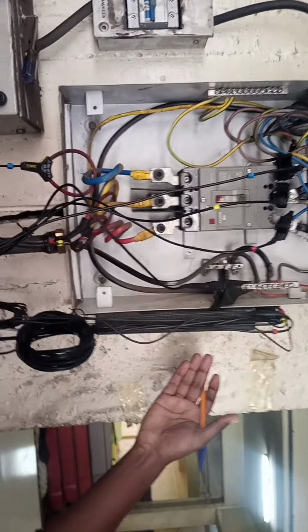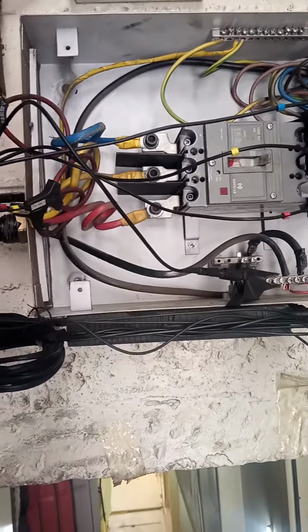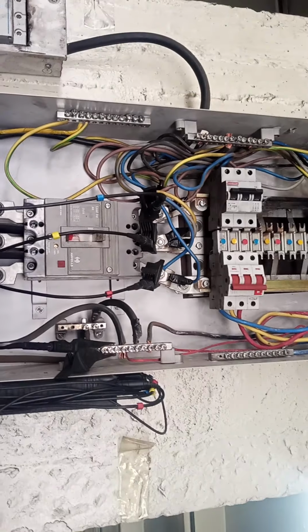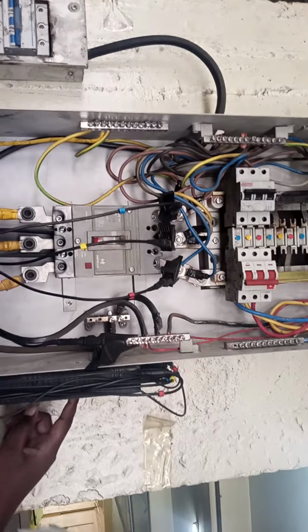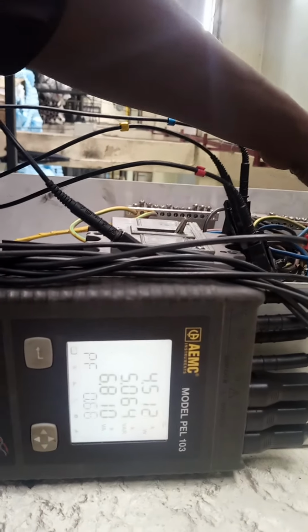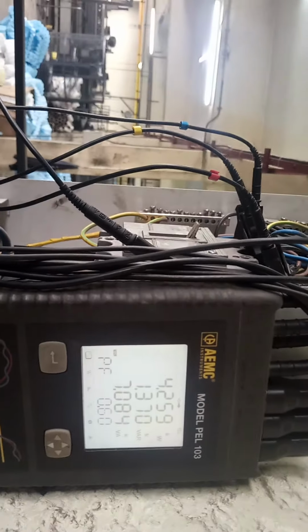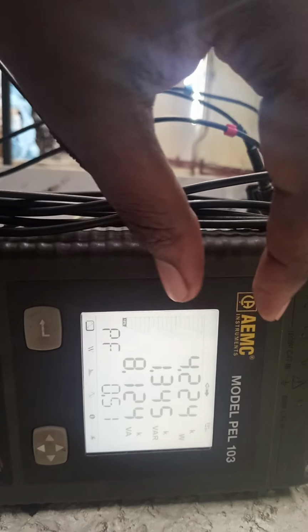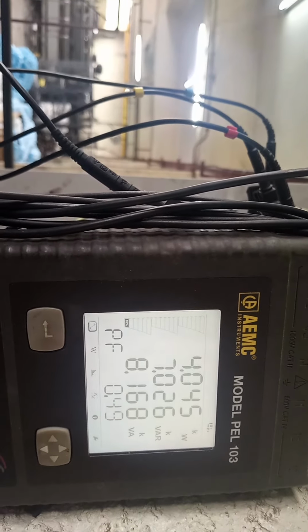So, meanwhile, if we are to stop the pocket machine there, you'll notice a drop in the consumption. If we check out the circuit breakers, I'll switch off the circuit breaker for one of the machines. Notice what is happening. We switched off. Notice now we are not going to the 5, to the 6 that we were going to. We are talking about a stable 4 because now it is one machine running.